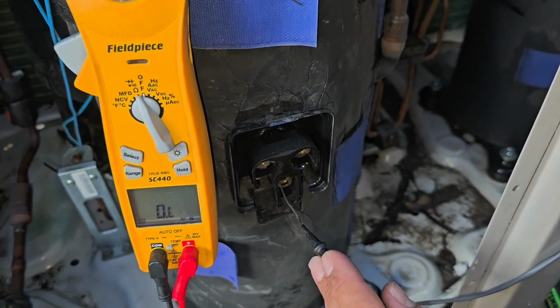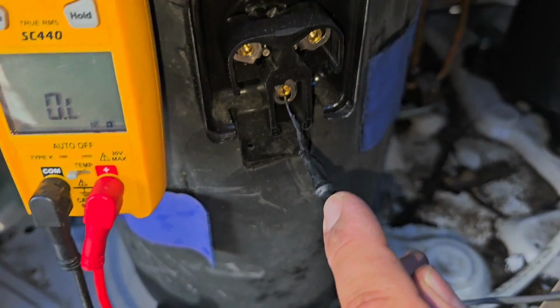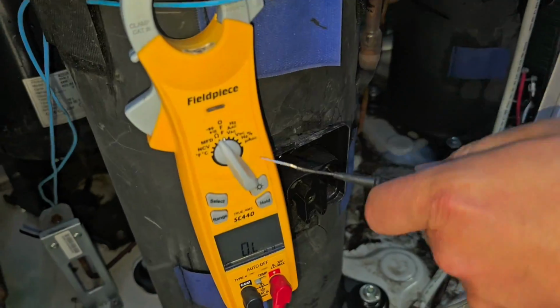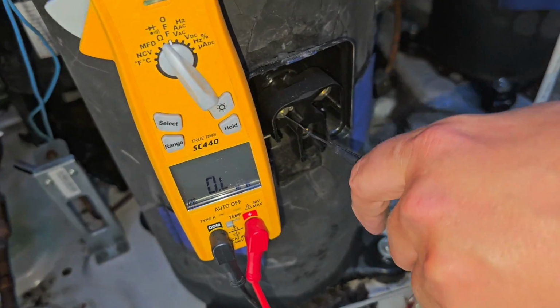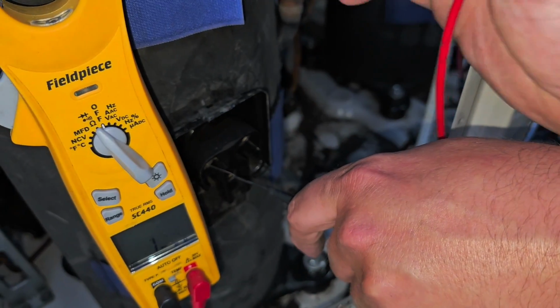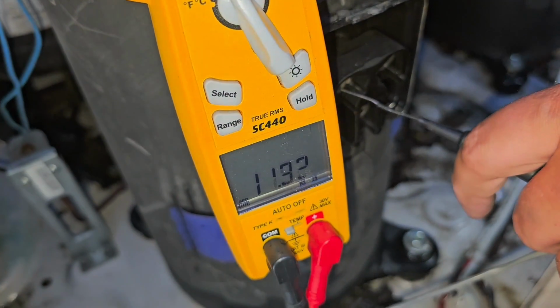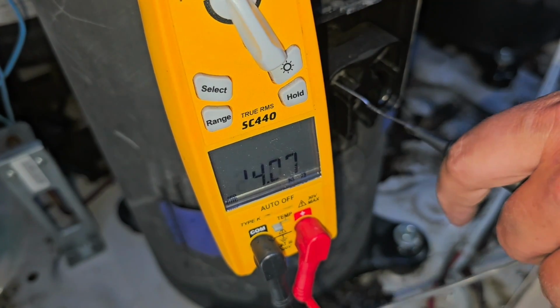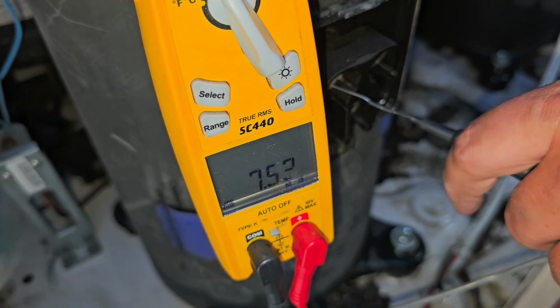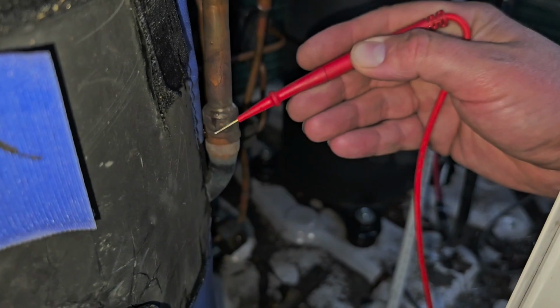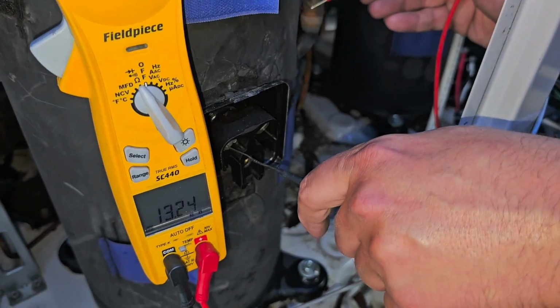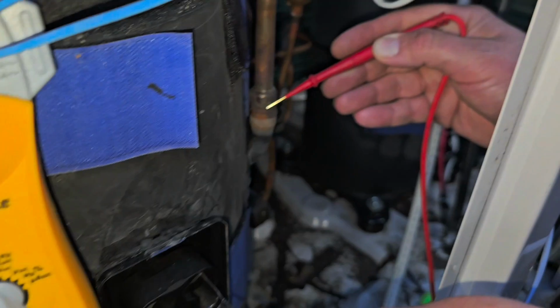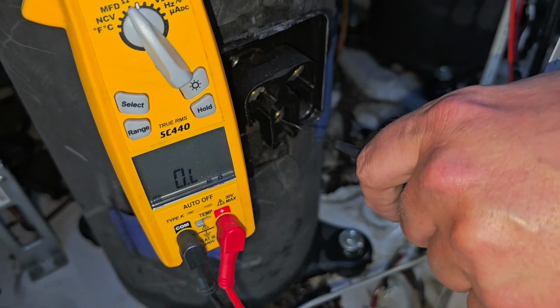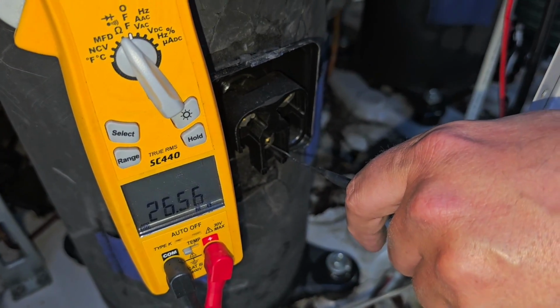Now the second test is we're going to go from 1 winding to the body. We're going to check each of the windings to ground. So take your meter, turn it to ohms, and then go from 1 winding to the shell of the compressor. Or you can go to the copper right over here. Let me show you. So you see how we've got a resistance reading, and we've got a resistance reading to every one of the windings. That means this compressor is shorted to ground.